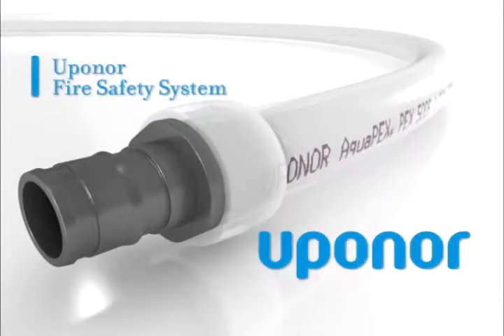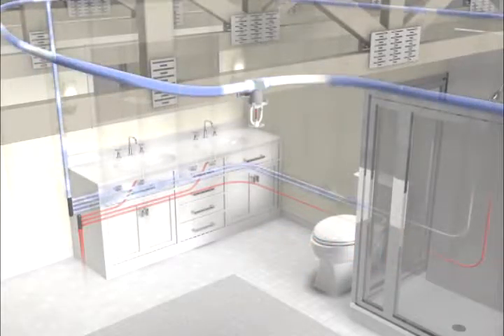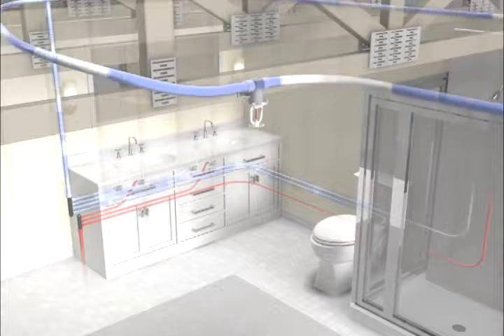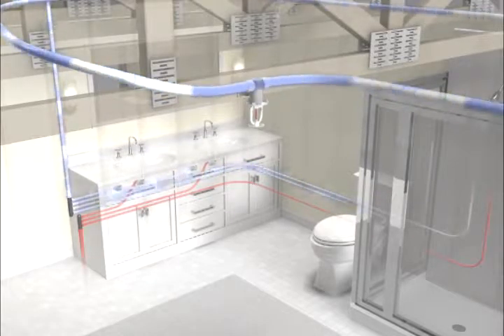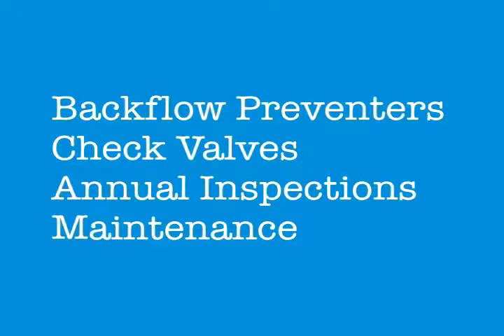Uponor's AquaSAFE multipurpose system is one of the most effective and efficient residential fire sprinkler systems available today. Since a multipurpose system integrates fire sprinklers with the home's cold water plumbing, a single contractor can now efficiently install both the sprinkler system and the plumbing system, and they can do it without any expensive backflow preventers or check valves, which also eliminates the ongoing inspection and maintenance of those devices.